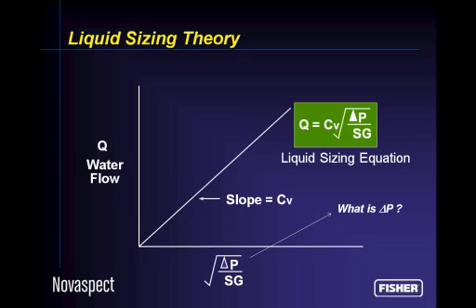If we were to plot that equation with Q on the y-axis and square root of delta P on the x-axis, we'd end up with a straight line with a slope equal to CV. Okay? That would suggest that if we can raise the differential pressure across the valve to infinity and beyond, as Buzz Lightyear would say, that would also raise the flow rate of water through the valve to infinity and beyond.